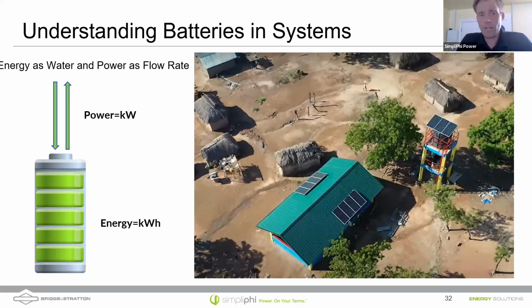I want you to think of the energy inside a battery similar to the water inside a water tank, right? There's a certain amount that's held. There's a certain amount of energy in a battery. There's a certain amount of water that a water tank can hold. That's the capacity of the battery. We typically refer to the capacity in kilowatt hours, or for very small batteries, watt hours. And we might use gallons or liters for tanks. But there's also the thing that's often forgotten, which is how quickly you can get the energy out of a battery. There's a power rating on batteries.